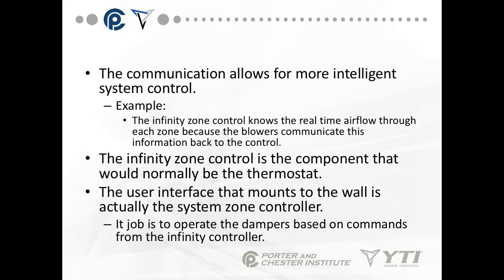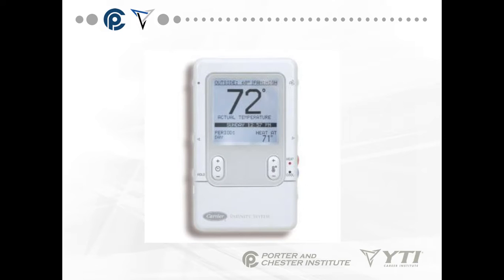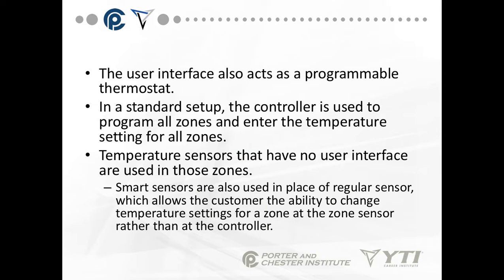For example, the Infinity control knows real-time airflow through each zone because the blower communicates this information back to the control. The Infinity Zone control is the component that would normally be the thermostat — the user interface that mounts to the wall. Its job is to operate the dampers based on commands from the Infinity controller. The user interface also acts as a programmable thermostat, used to program all zones and enter temperature settings. Smart sensors allow the customer the ability to change the temperature setting for a zone at the zone sensor rather than just at the controller.